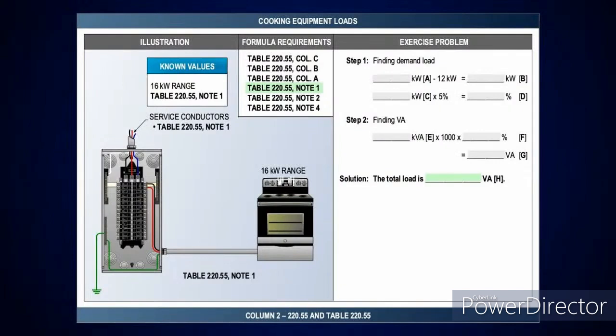Well, thank you. And this is the same one. I'm over 12 kW, so I've got a 16 kW range. I'm taking 16 kW and I subtract the 12 because it's rated up to 12 kW. That's going to give me 4 kW. Then that's for each additional kilowatt that I have there. I'm going to take that at 5%. And then I have one unit. Once again, I'll take 8 kW, and I can tell you it's going to be multiplied at 120%.